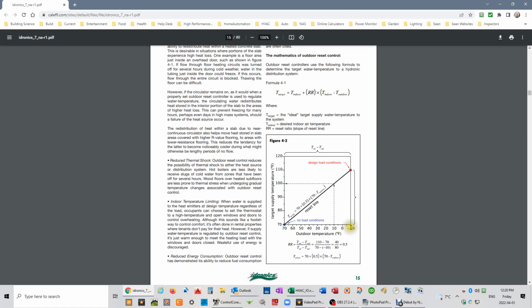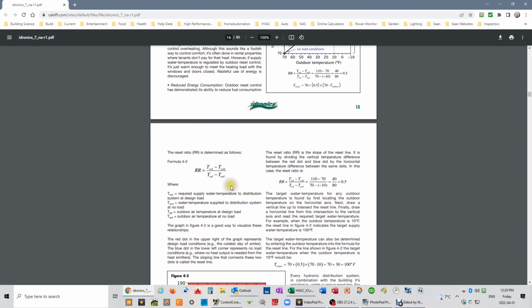So your coldest day of the year, what is the required temperature you're going to need to meet the heating requirements of that coldest day, and that sets the ratio. And then the other side of it would of course be the outdoor temperature being equal to the indoor temperature. And that would be 0 requirements, 100% of requirements. This line creates what's called a reset ratio, and that is calculated by the required supply water temperature to distribution system at design load.